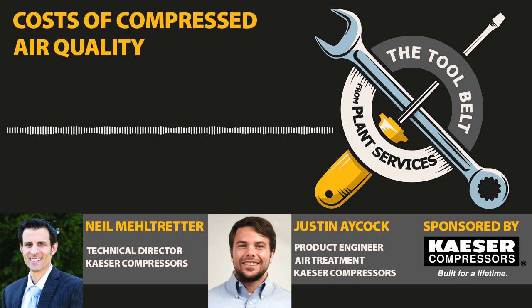So the velocities, as Justin mentioned, could be relatively high, and that means that we don't have enough contact time for air treatment. It also means that as we get faster in the distribution network, over 30 feet per second, then we start to see turbulence effects. So normally speaking, when we're talking about drops and points of use, as you go faster, you're going to be potentially pushing, if there's any liquid water in the system, which it certainly could be if you have high velocities, you're pushing that water down to the point of use.